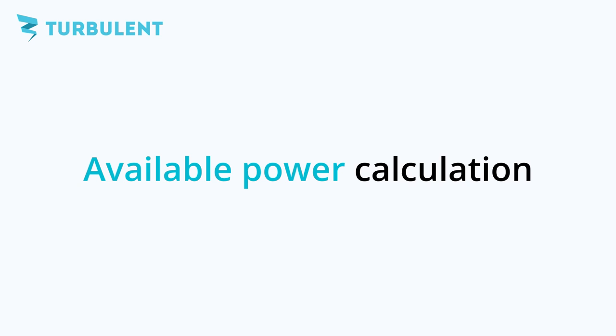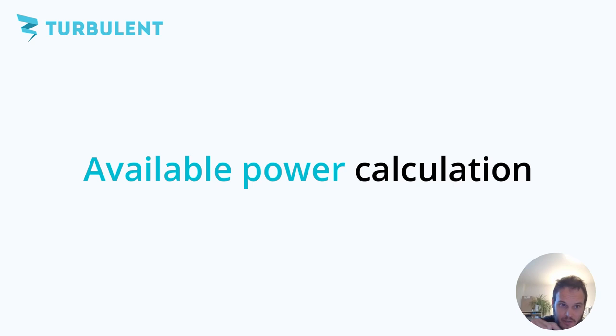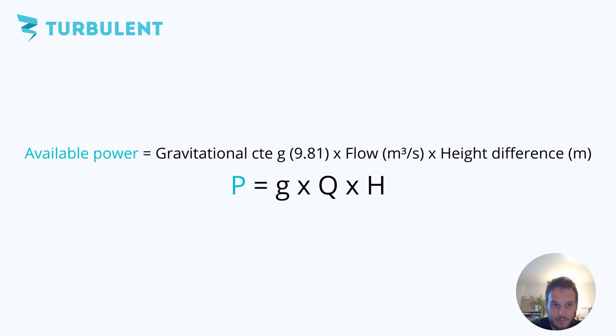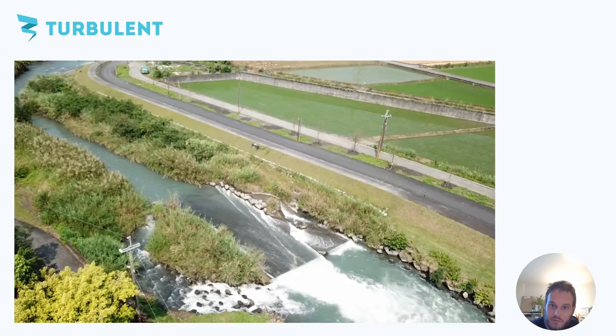Let's get back to the formula. So now we have everything we need to calculate the total power of the site that you have found which is as I will repeat the hydraulic power available is equal to the gravitational constant g which is 9.81 times the flow in cubic meter per second which you have just calculated using the float method times the height which you have measured with your topographic station or your water level. All of this together will give you the hydraulic power that you can get out of your turbine and you can multiply that as a rule of thumb by 0.6 to get the electrical power that you will get out of this site.